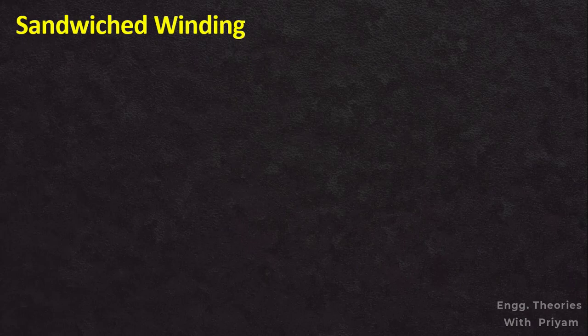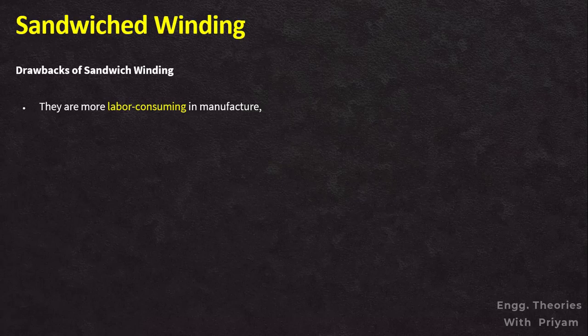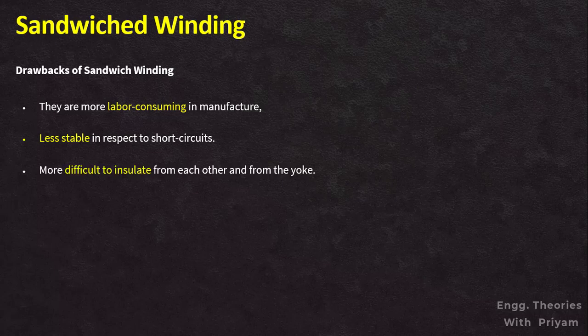Drawbacks of sandwich winding: in comparison to concentric winding, they have several drawbacks. They are more labor-consuming to manufacture, less stable with respect to short circuits, and more difficult to insulate from each other and from the yoke. This is the reason why core-type transformers with concentric windings are more common.